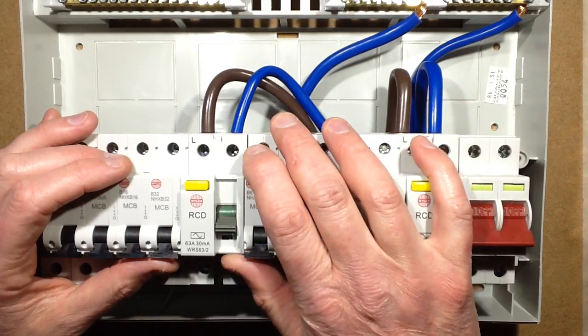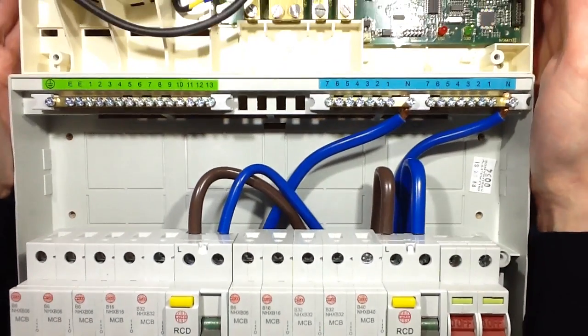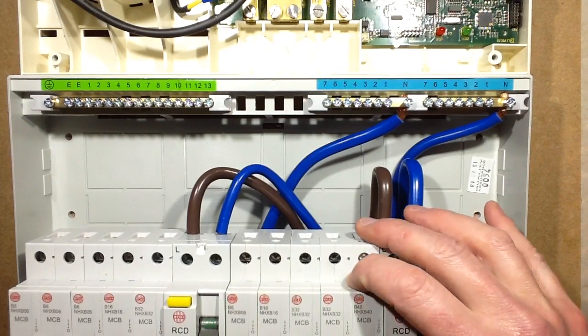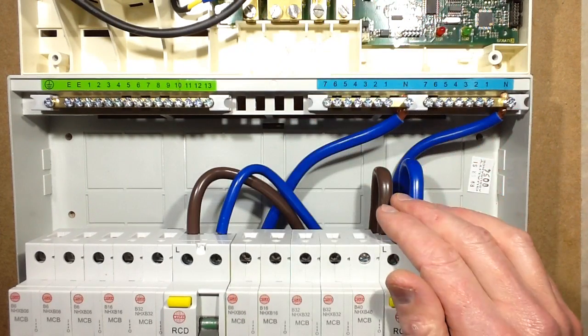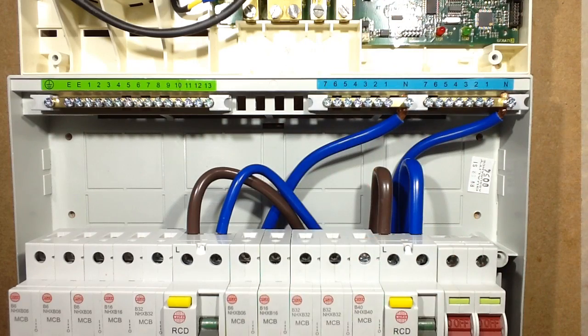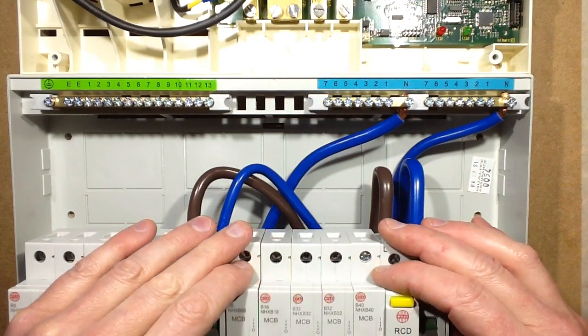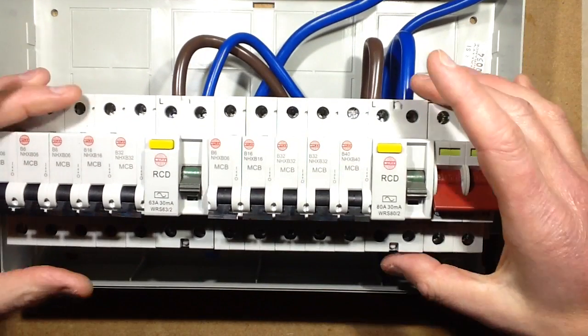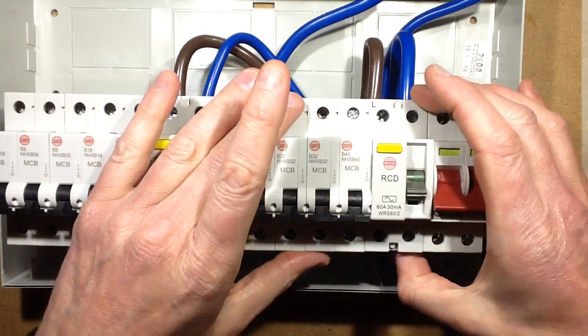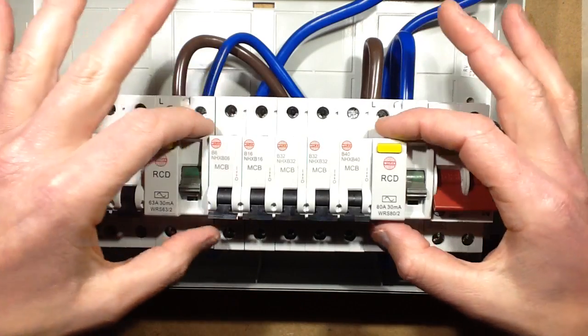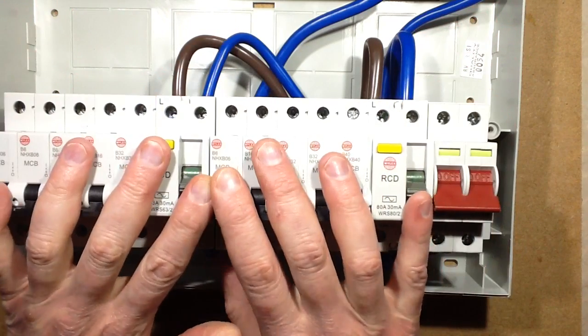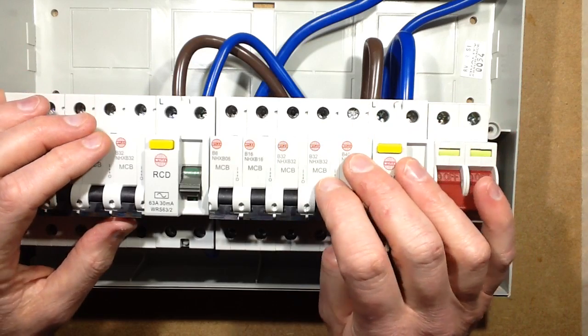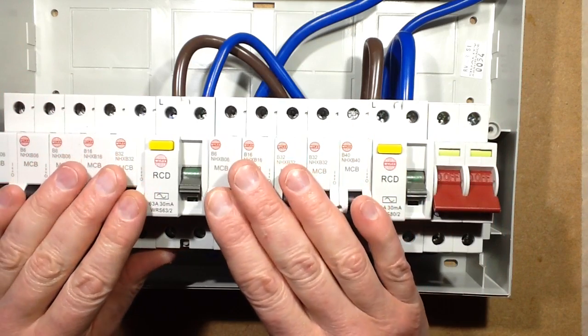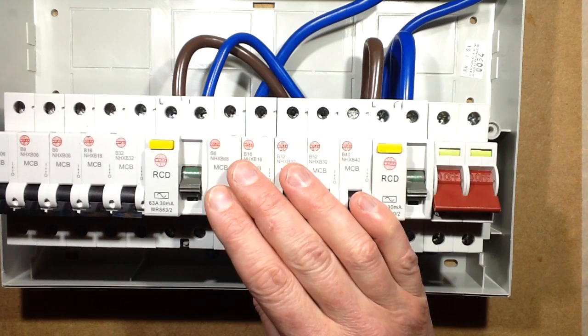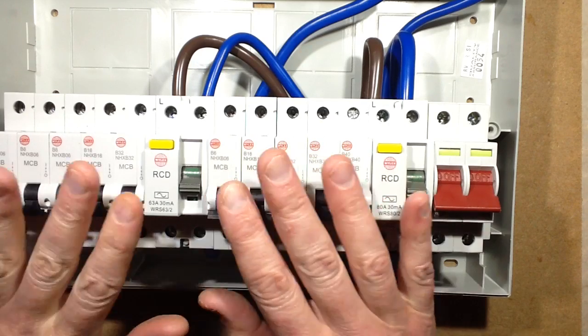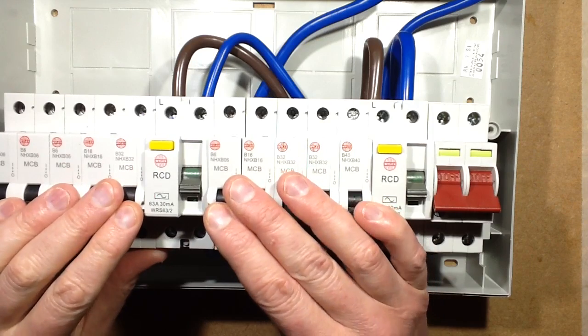But anyway, to actually put this big chunky unit in, you have to put in an extra breaker, a 50 amp breaker, to feed that unit. And then that has to come back and feed a set of dedicated circuit breakers. So there are some significant modifications required. In the case of this, you'd have another link coming out, going through the 50 amp breaker, and then coming back and feeding, say, this bank of breakers. It wouldn't feed the whole house because it's not rated to feed heavy heating loads like showers, which is going to be one of the highest loads in a house, or electric heating, or water heating. They say it's really just for things like lighting and ring main circuits and circuits in your kitchen.